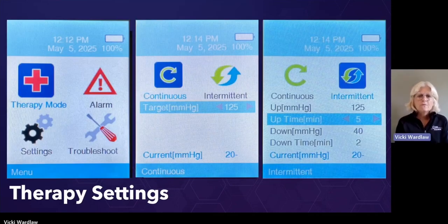From your home screen, if you press the menu select button to go to the first menu, this is what you'll see. Therapy mode is highlighted. That is what it looks like when an icon is highlighted. Therapy mode always comes up highlighted first because that is typically where a clinician will go if you go anywhere. You also have alarm, which is the red triangle. I'll show you what's there. We have troubleshooting, which is the wrench and the screwdriver. I'll tell you about that as well.